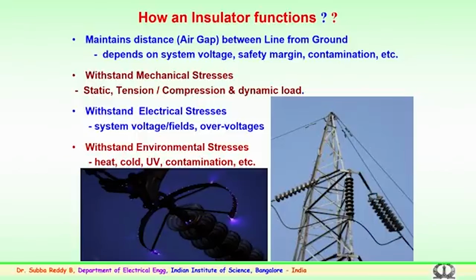Apart from mechanical and electrical stresses, these insulator strings have to withstand environmental stresses like temperature: very high temperature areas where the transmission system is erected, and the second being cold areas, like very high altitudes, where the temperature comes down drastically. So, they have to function in that environment, and withstand ultraviolet radiation, particularly from the sun, and also UV radiation sometimes arising because of the corona effect.